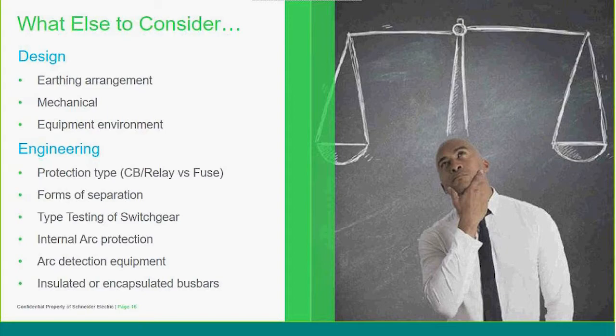Protection types, circuit breakers, relays versus fuse. These are all very important points when you're considering upgrading your system. Have a consideration of the incident energy levels, the fault levels, and the tripping times. Internal arc protection, arc detection equipment. There is technology now that inside a switchboard can detect light of the right spectrum and the magnitude of current coming in to determine that I have had an arc flash internally in the bus bars. What that tends to do then is to ignore any protection timings and initiate an instantaneous trip to the protection.